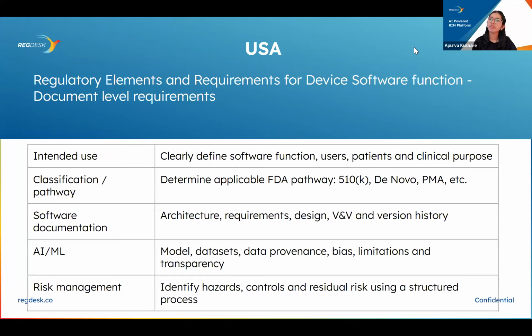So we will go through the regulatory requirements. As you can see here, on the left-hand side I have listed the regulatory elements, and on the right-hand side the requirements for the software device functions and some key documentation required to comply with the regulations in these particular markets. The first and most important thing is the intended use. It is very important for manufacturers to clearly define the software functions, the users, patients, and the clinical purpose. Sponsors should also consider the risks in the context of the device's intended use. It is also important for the manufacturer to first determine the applicable FDA pathway.